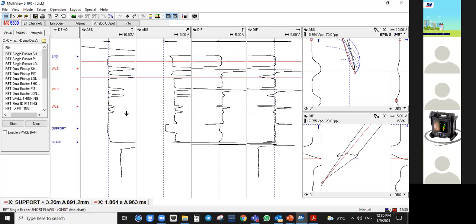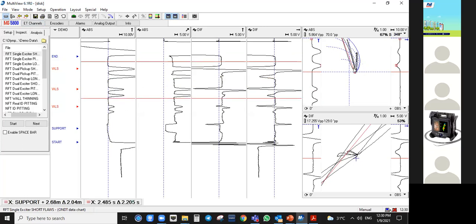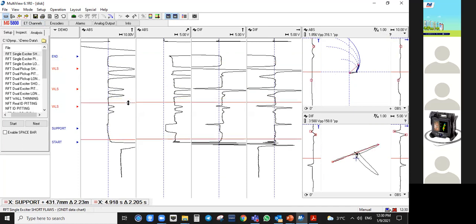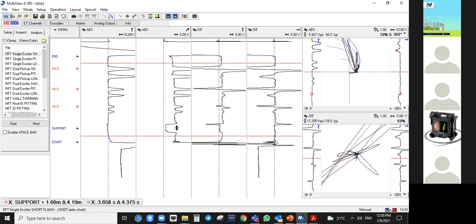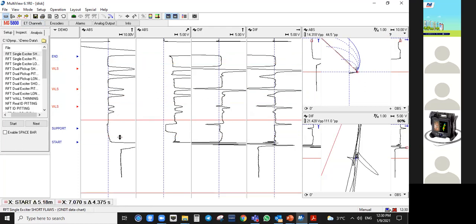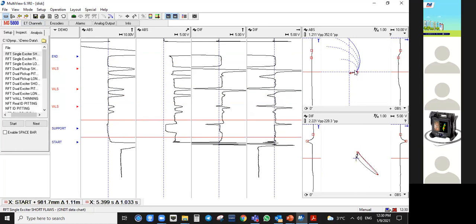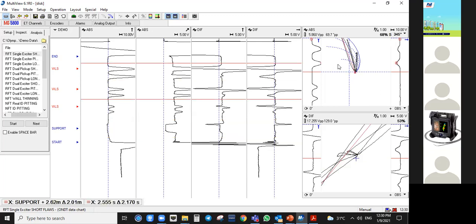Once you run it again, make sure that the difference is 20. And then just make sure that you also need the support. So that's the support here. It's quite hard to explain now without the equipment and the probes, but this is how we usually calibrate. First, you change the frequency so that this separation is around 20 degrees.